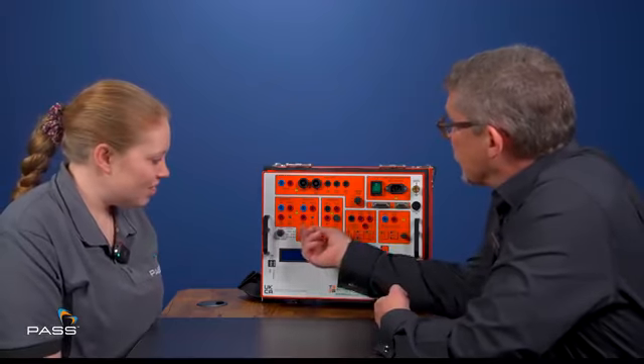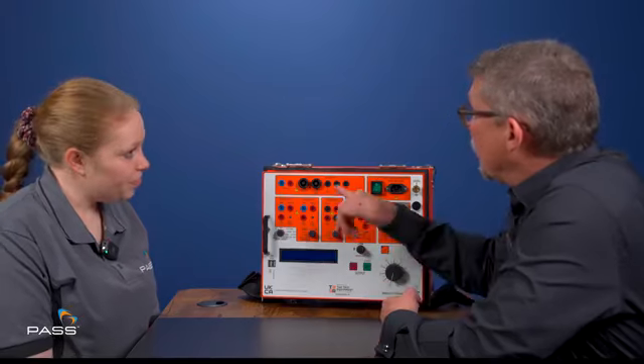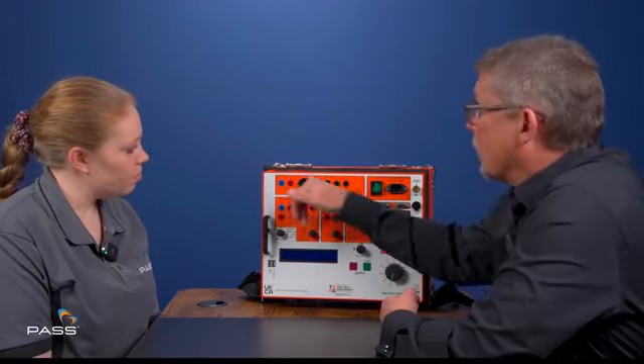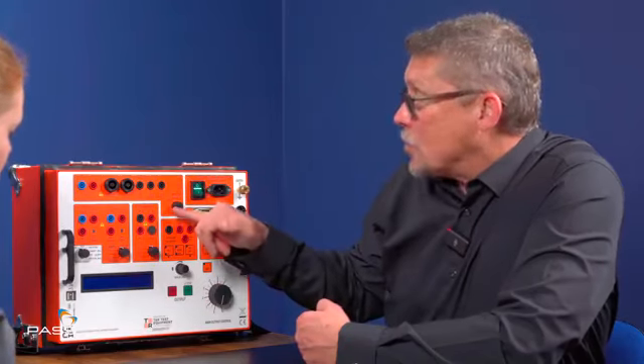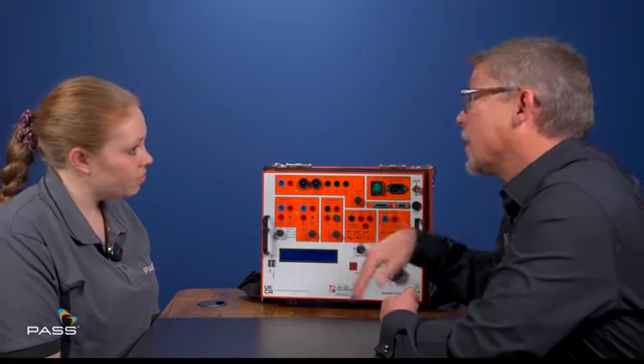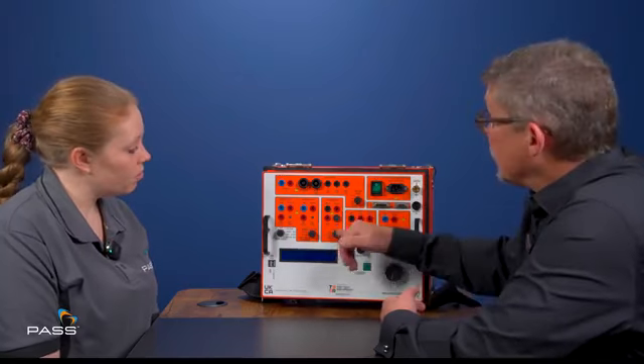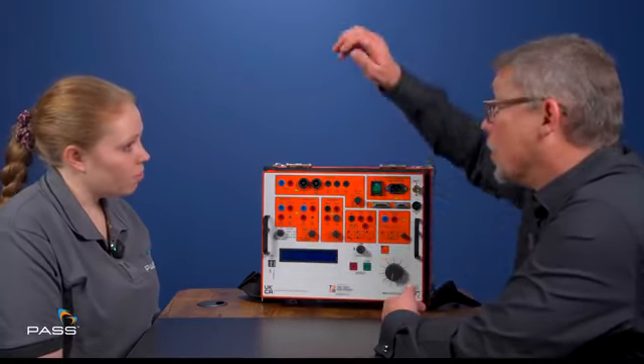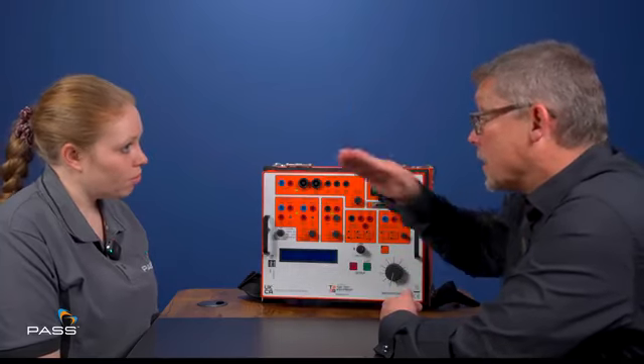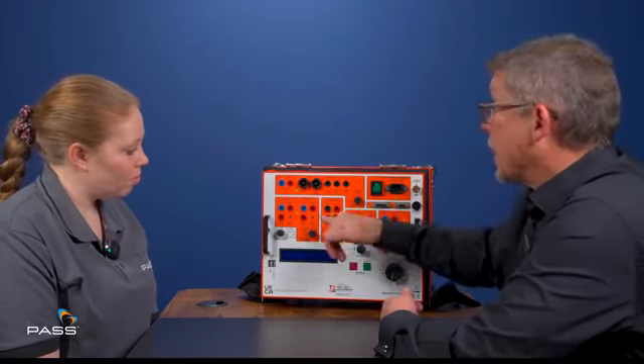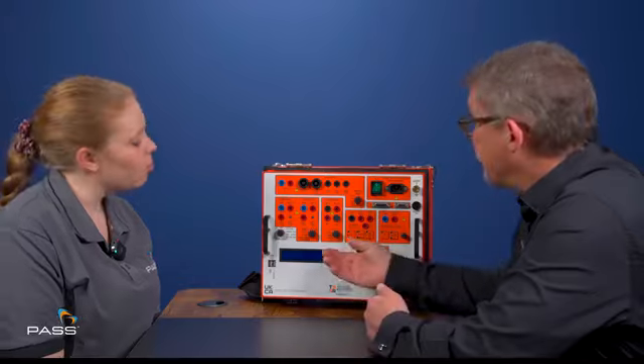Okay, the next section here is current operated. And what that means is when it sees current flow through here of 10% more than the range that you're in, it will start the timer. And when it sees the current stop, it will stop the timer. And that is, again, so you could set the current output, shut the breaker, current flows out, trips the breaker, and it measures the start and stop time.